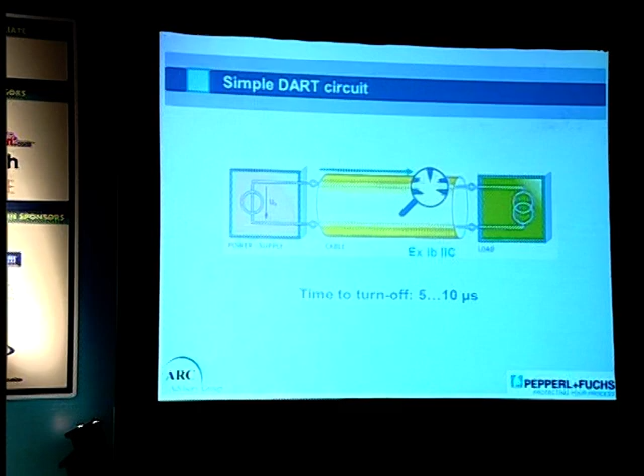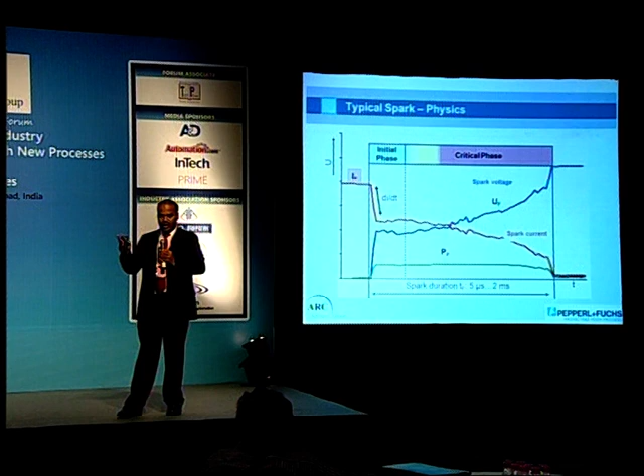At the same time, because it's an inductive circuit, the cable is nothing but a combination of inductance, and it's going to build up a voltage until a certain level, after which it goes back to zero. This is the electrical characteristic when you cut the cable: the current drops to zero, the voltage builds up, and after that it goes back to zero. But during this time, the power stays constant because it's a product of voltage and current. Even though one factor decreases and the other increases, the power remains constant for a few milliseconds, and that's enough to create a spark in the cable. The critical phase is defined in the millisecond region, while the microsecond region is the initial phase, where the dropping and increasing take place. This is what happens in the normal unlimited energy circuit.